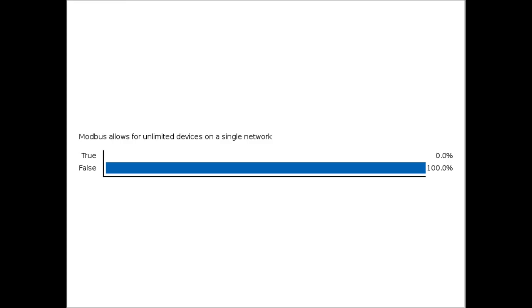Pop quiz: true or false — Modbus allows for unlimited devices on a single network? The correct answer is false. Modbus does allow multiple devices on its network, but it is limited to 247 devices. This limit exists because every device needs its own unique address or identifier, and addresses can only be set between 1 and 247. So you can have a lot of devices on the network, but it's not unlimited.